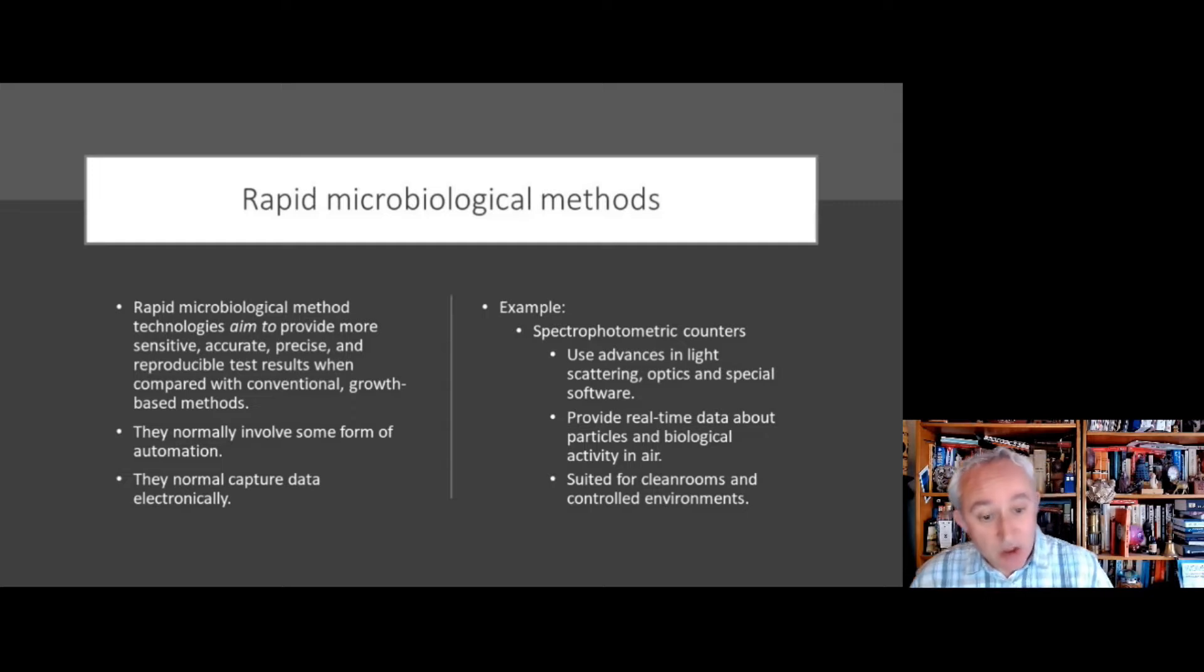And this is achieved through two detectors. First of all, there's the conventional detectors you get in a standard optical particle counter, and then there are detectors that are based on fluorescence detection looking for these biological particles. They're looking for three biological markers, three metabolites: NADH, riboflavin, and DPA. DPA is the acid component of bacterial spores.